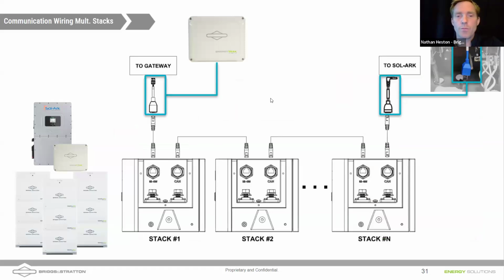If you've got multiple stacks of batteries, you can parallel these batteries, and you just need a single one of those battery controllers to connect directly to the SolArk. If you are using our Energy Track gateway, you can connect it to the first RJ45 port. Or if you're not, you could just put a terminating resistor in that first connection. A CAN bus chain is expecting a big loop, and you need to tell the computers on that chain where the last battery is. And so either we use the gateway, which has a built-in terminating resistor, or we put a terminating resistor in this dongle.